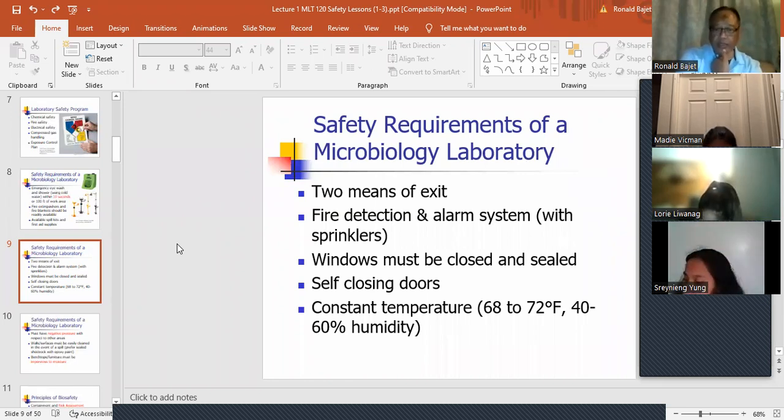And that's actually, those are the ambient conditions, but it's more for the instruments, because a large change in temperature or a large change in humidity can affect your instruments and QC. You'll notice that on hot days your QC will go out of whack. So that's something to be careful about.